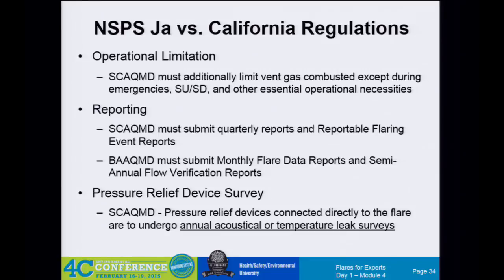They do require this, something nobody else has, only in California: the pressure relief device survey. So South Coast, those seven refineries, have this annual acoustic or temperature leak check on every relief device into the flare header. Not everybody does that. It's a good management practice that a lot of people seek to do using the VPAC2 or some other acoustic device, walking around surveying the plant. We've done quite a few of those as well. It's voluntary, there's nothing in JA that demands it. It's only required, we think, at South Coast. But there's some interesting stories we can tell about those acoustical surveys if you're interested.